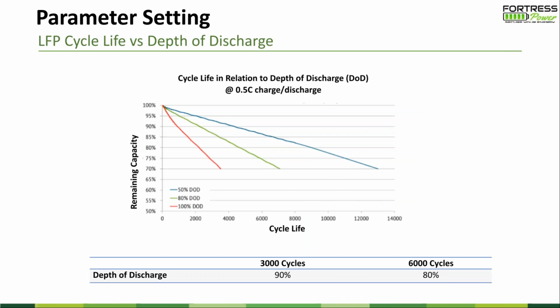Next slide, please. And we also talk about not squeezing too much energy out of the battery. It will impact your life cycles. This picture shows you perfectly. If you do 50% depth of discharge, it's going to last super long. At 80%, 6,000 cycles puts you at about 75 to 80% of left capacity. If you do 100% depth of discharge, at 2,000 cycles you're probably already at 75%. This just gives you some understanding of why we don't want the customer to use the battery in a full discharge situation. Next slide, please.